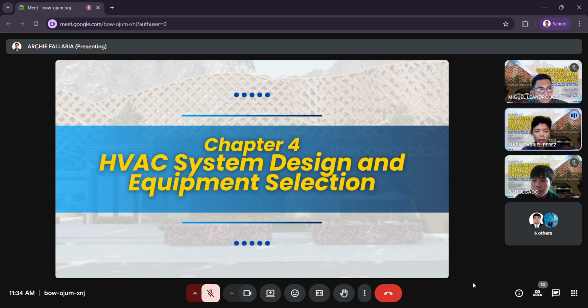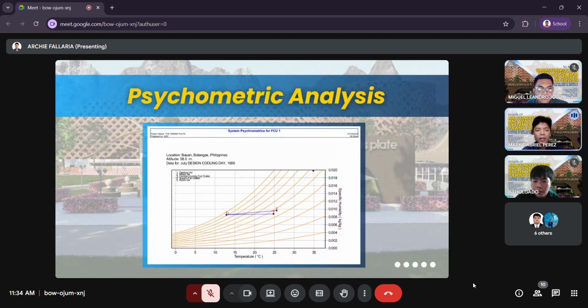For the next chapter, we have HVAC system design and equipment selection. First is the psychrometric analysis. Psychrometric analysis looks at the temperature, humidity, and other air properties to help design HVAC systems that keep indoor spaces comfortable. Using a psychrometric chart, the air process for FCU1 on a typical July afternoon in Bauan, Batangas was mapped out. Hot and humid outdoor air at 34 degrees Celsius mixes with return air to bring down its temperature and moisture. It then passes through a cooling coil and drops to 14.5 degrees Celsius after being slightly warmed. It enters the room at 25 degrees Celsius with balanced humidity.